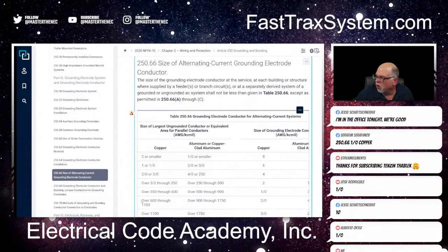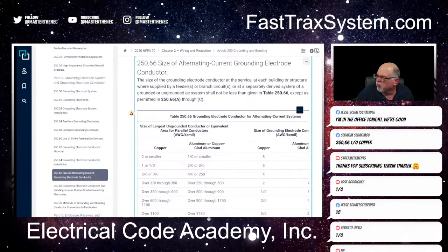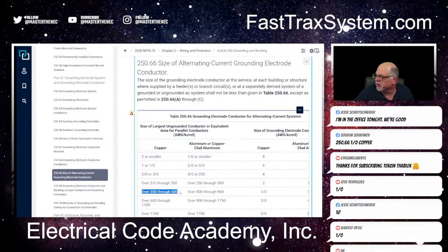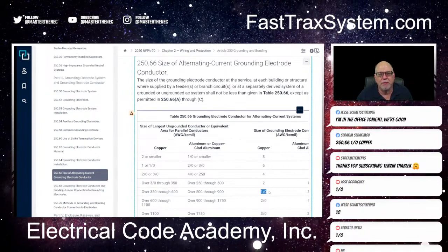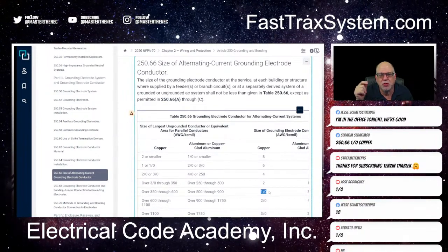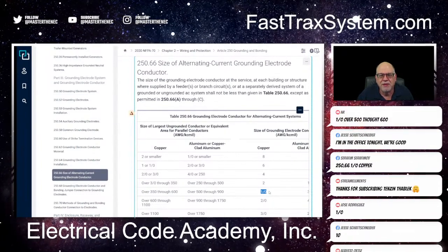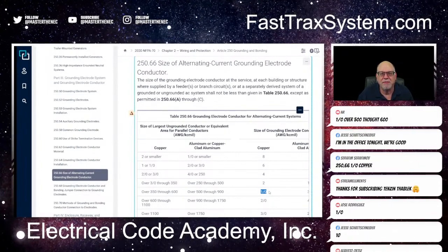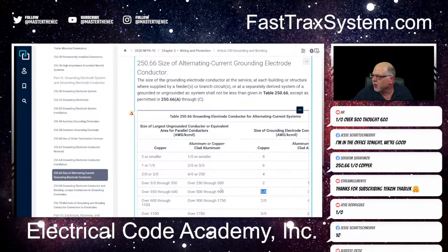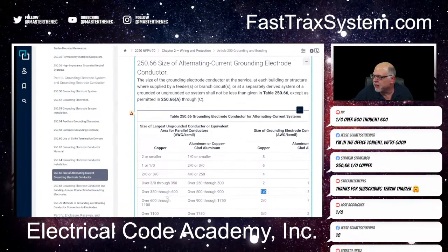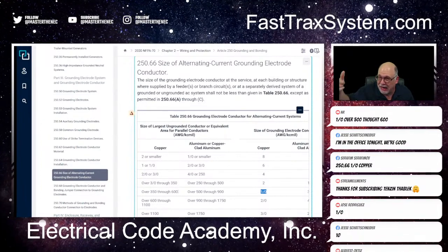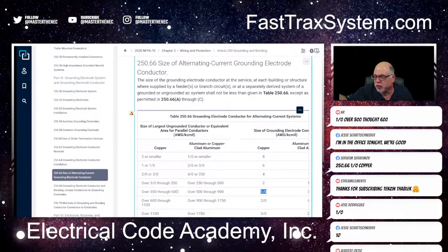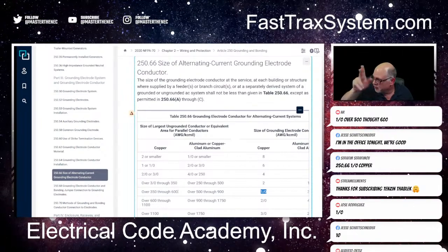So we're not over 600. We are over 350 through 600. And that means it would be a 1/0 copper. And you all nailed that. Everybody in there was posting, boom, boom, boom, boom, boom. All right? So, okay, makes sense. It's actually over 350 through 600. My eyes are bad, but I believe it says over 350. But you got it. Same concept.